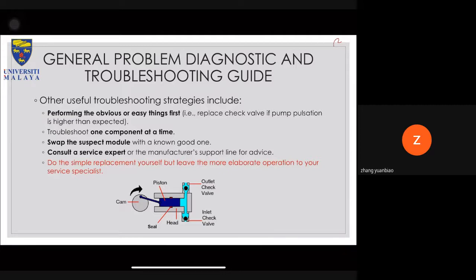Okay, so other troubleshooting strategies include performing the obvious or easy things first. For example, you might want to replace a check valve if pump pulsation is higher than expected. Or you want to troubleshoot one component at a time, because if you troubleshoot everything in one go, you will definitely resolve the problem, but it might take a lot of time to identify the main cause of the problem. You can quickly identify what the problem is, but to identify the cause, if you run all modules simultaneously, it might be difficult and time consuming.